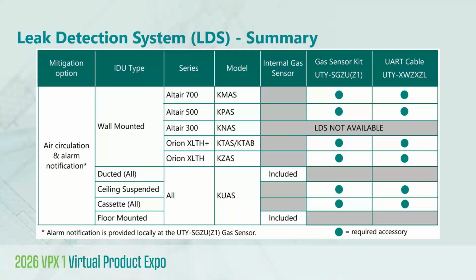Now, let's talk about the summary of the compatibility between the LDS accessory and the H-Series models. As you can see, the IDU type, we have listed all the different IDU types we have: the wall-mounted, ducted, ceiling suspended cassettes, and the floor-mounted. And under the wall-mounted, we have listed all the series that fall under the wall-mounted section. And as you can see, except the KNAS Altair 300 family, the rest of the wall-mounted models are compatible with the gas sensor kit. Down below, we can see that the ducted and the floor-mounted include the leak detection sensor, built in from the factory. The ceiling suspended and the cassettes will be compatible with the accessory similar to the wall-mounted units, and they all will need the UART cable.